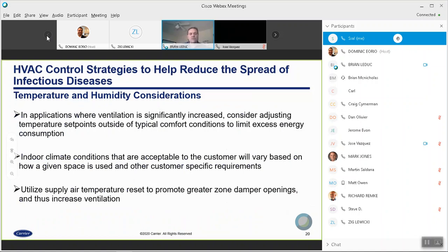If the customer does choose to increase ventilation, it might be beneficial to consider expanding the temperature set points a little bit outside of the traditional comfort conditions, just as a means of limiting the excess energy consumption that's going to come along with increasing the ventilation rate. So again, there are going to be limits to how far you can go with that. It's going to be up to the customer to decide, but particularly in the warm weather months, allowing the temperature in the space to creep up a bit above their normal comfort conditions can help offset the increased energy consumption that increasing ventilation is going to provide.